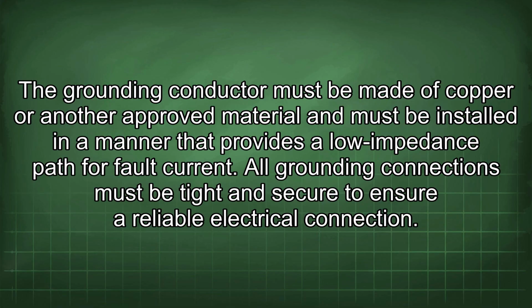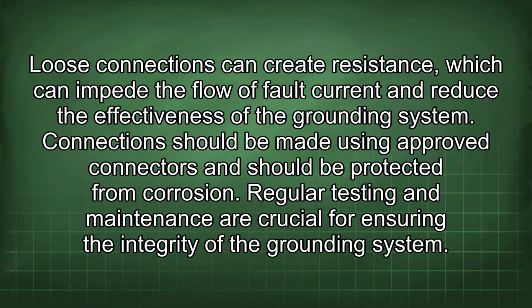All grounding connections must be tight and secure to ensure a reliable electrical connection. Loose connections can create resistance, which can impede the flow of fault current and reduce the effectiveness of the grounding system. Connections should be made using approved connectors and should be protected from corrosion.